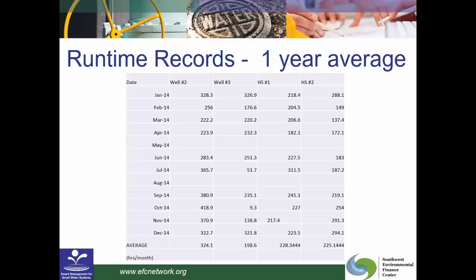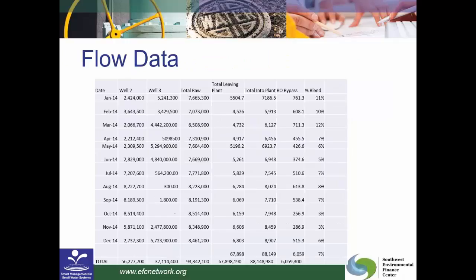I talked about averaging data and the information that you collect in the field or that you collect in the office. So this is an example of calculating your average run times for each piece of equipment, and this is using Excel. So we had a monthly total hours for each well and each high service pump. We added them up for the course of a year and averaged them out. And then we use these average numbers in our spreadsheet to look at the total hours per year. This is an example of calculating your total flows for 1 year. So again, we had monthly data. We put each month's information into the spreadsheet, and we let the spreadsheet find a total for us.